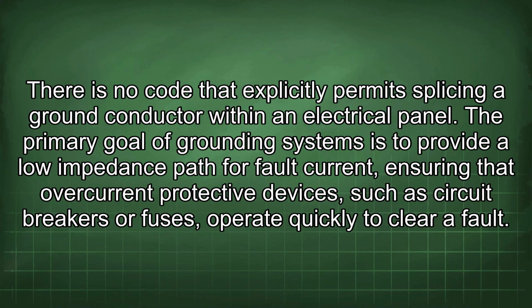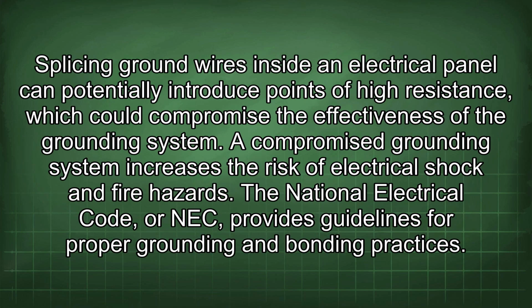There is no code that explicitly permits splicing a ground conductor within an electrical panel. The primary goal of grounding systems is to provide a low impedance path for fault current, ensuring that overcurrent protective devices, such as circuit breakers or fuses, operate quickly to clear a fault. Splicing ground wires inside an electrical panel can potentially introduce points of high resistance, which could compromise the effectiveness of the grounding system. A compromised grounding system increases the risk of electrical shock and fire hazards.